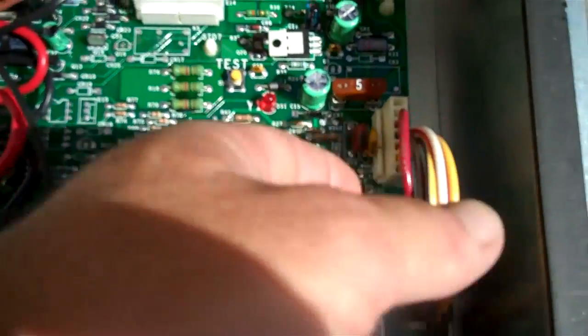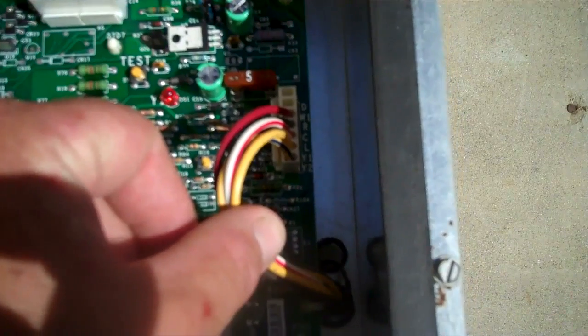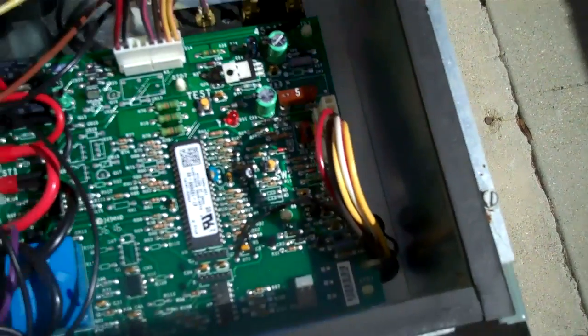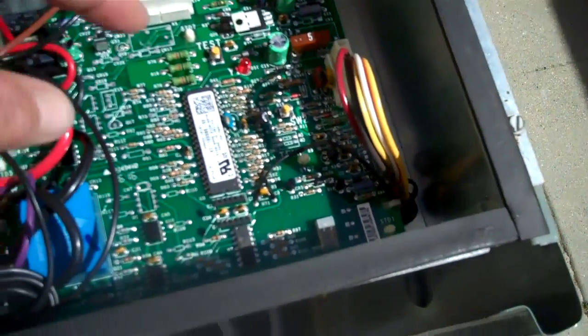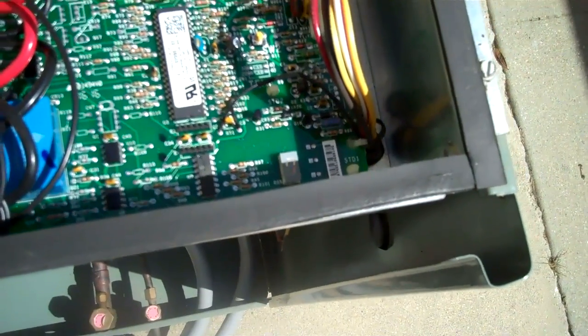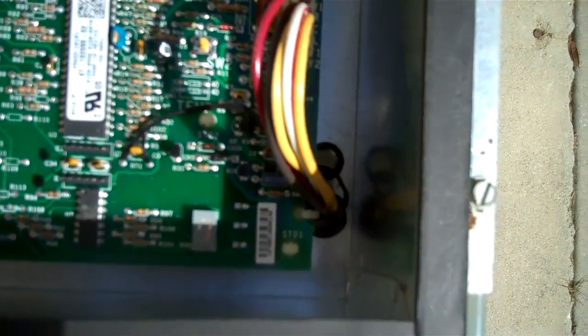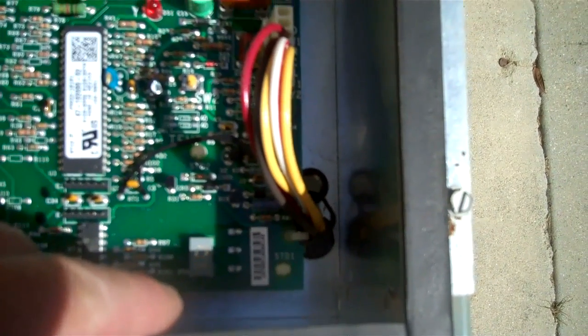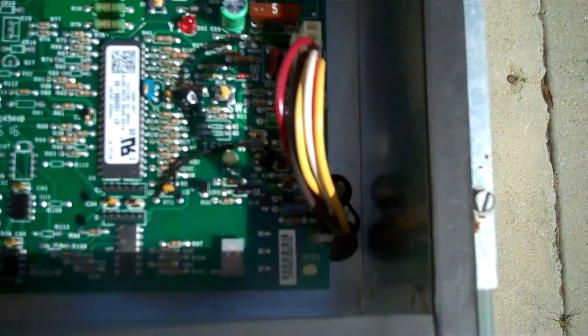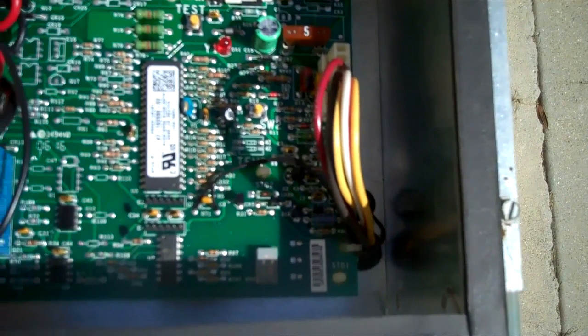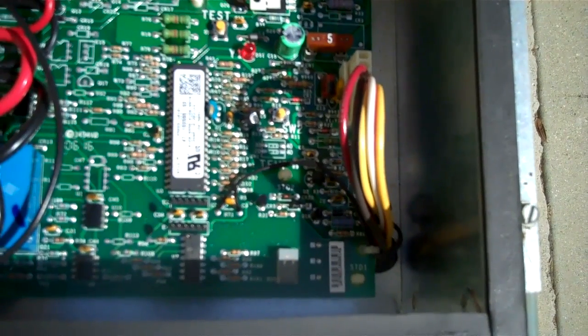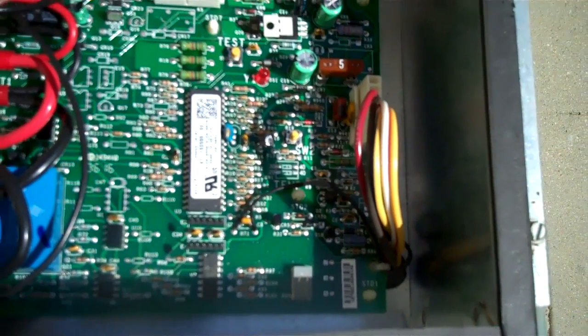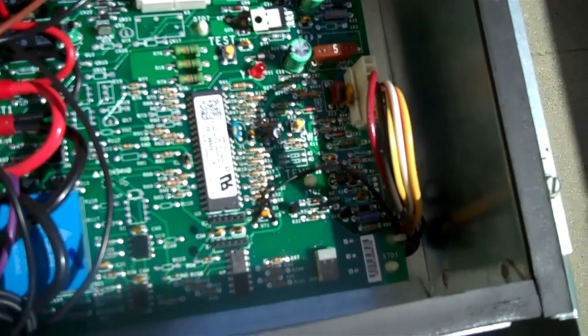These are all your low voltage wires, R, C, L, Y1, Y2, you got your fuses, and then you have, I don't know if you can see it down here because of the sun. This is what tells you what's going on with the unit, little LED. Zero is for when it's not running. Little C is first stage cooling. Big C is second stage cooling. It has fault codes like 27 is no power, no 230 volts.